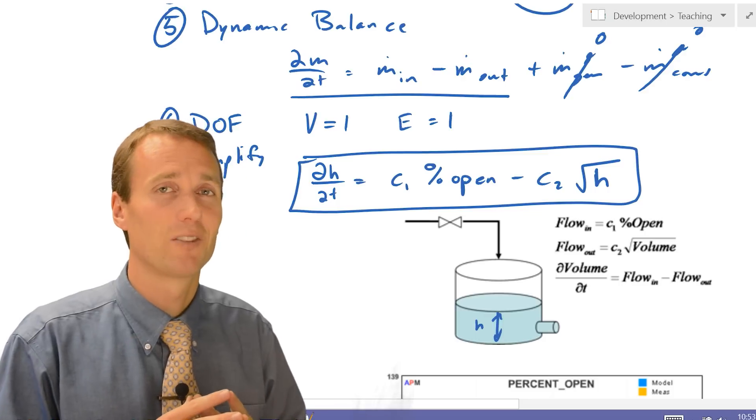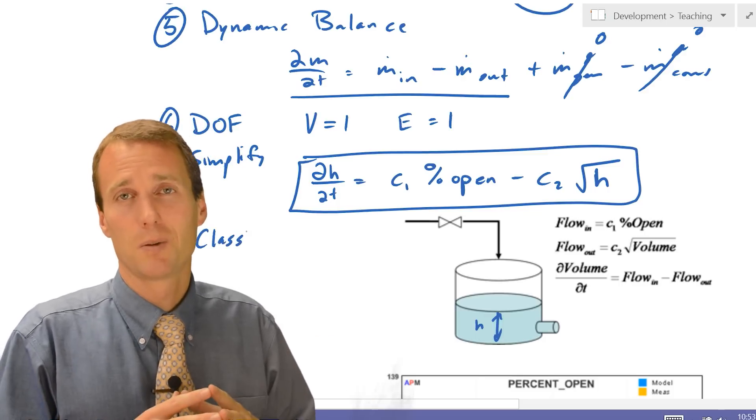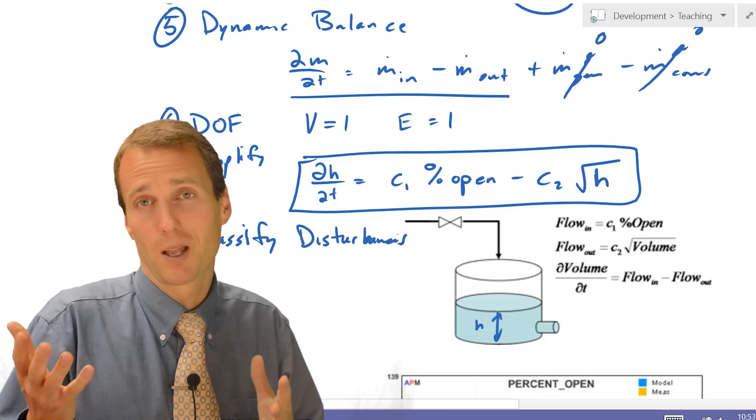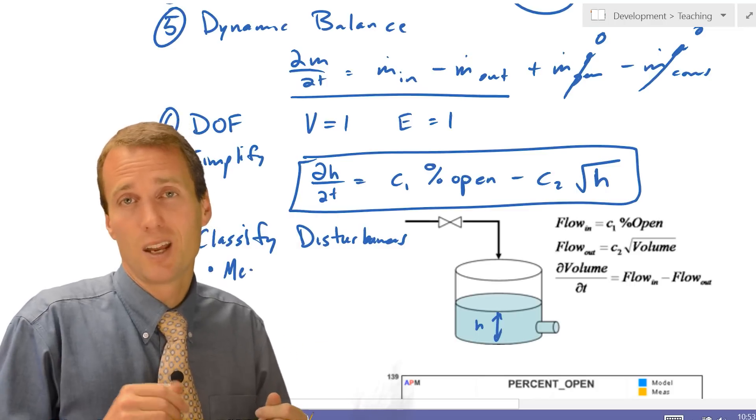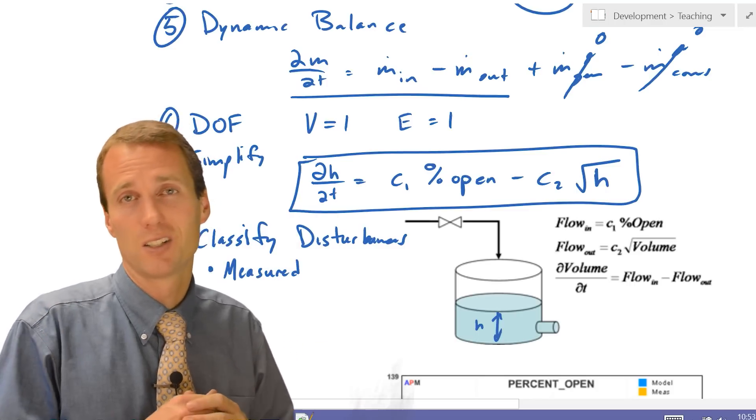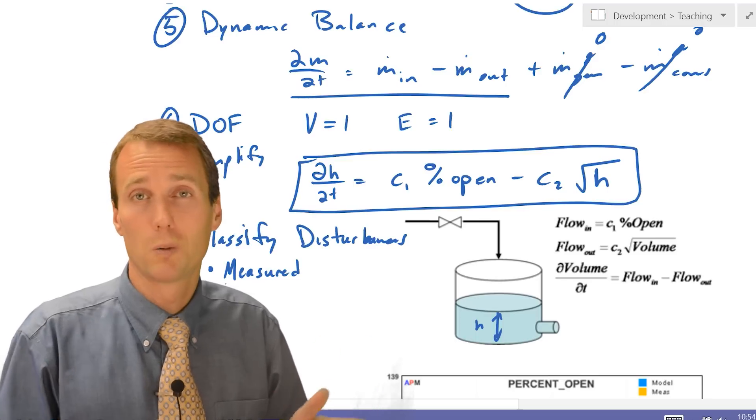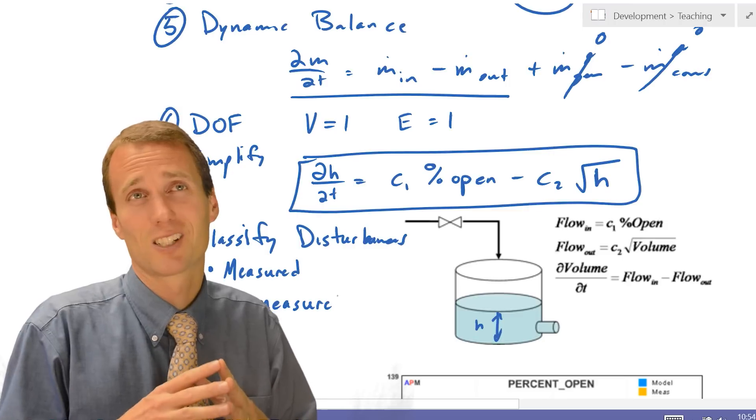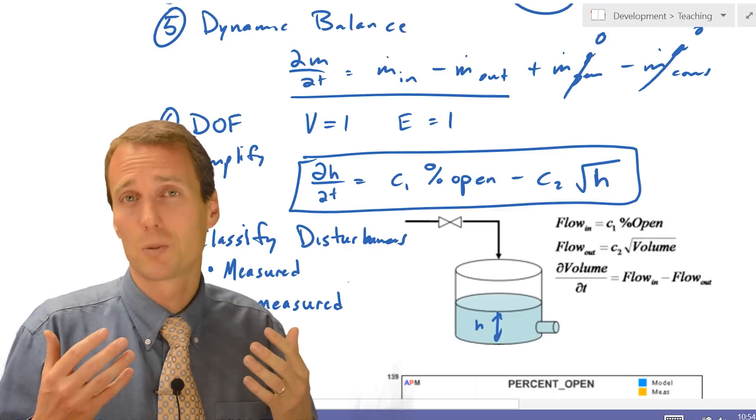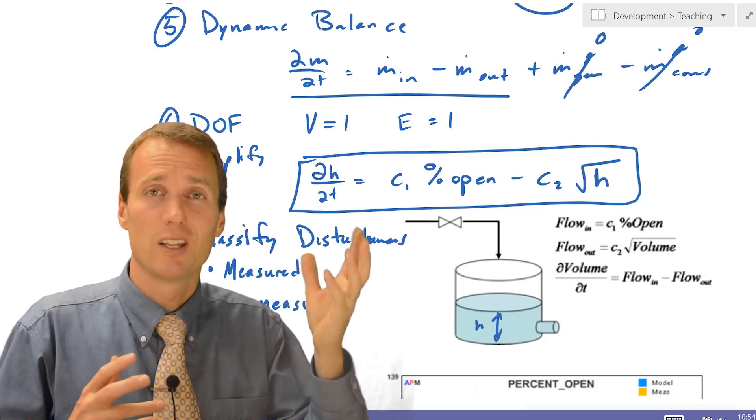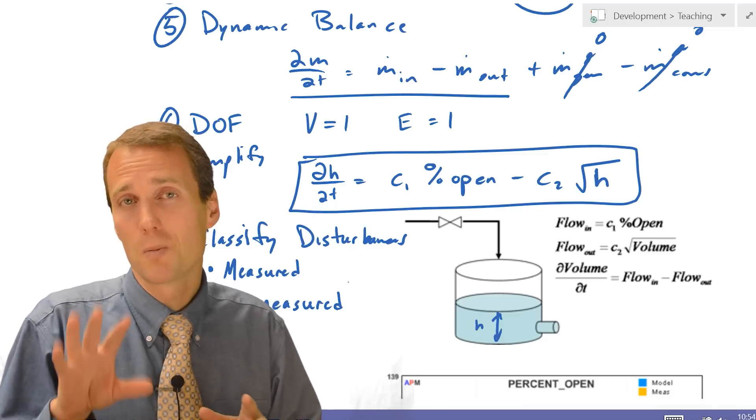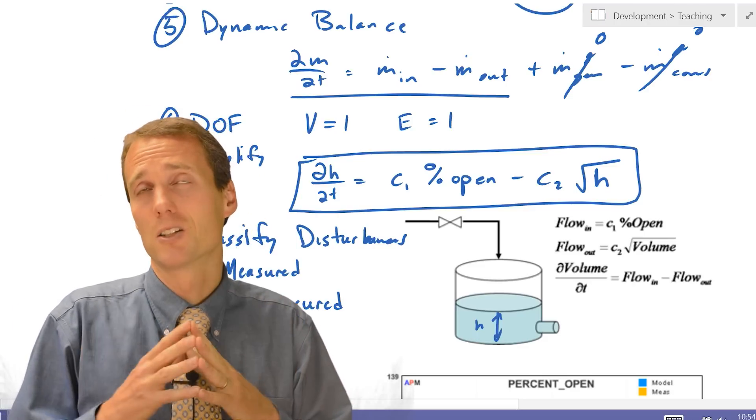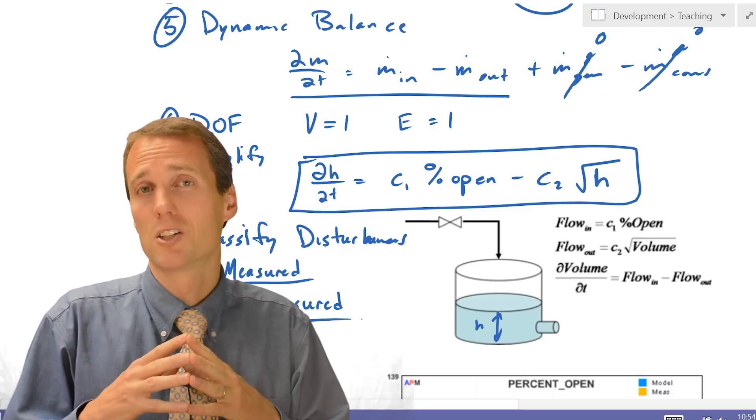The final thing that we can do is go ahead and classify disturbances or other inputs that we have coming into our system. So in this case, you might have the city water supply pressure that changes. That might be a disturbance. And we can maybe install a pressure sensor on that supply line to have a feed forward into our controller. Some disturbances you can measure, and some are unmeasured disturbances. So it's important to classify the different types of disturbances that may be affecting the process, and just classify those as measured or unmeasured disturbances.